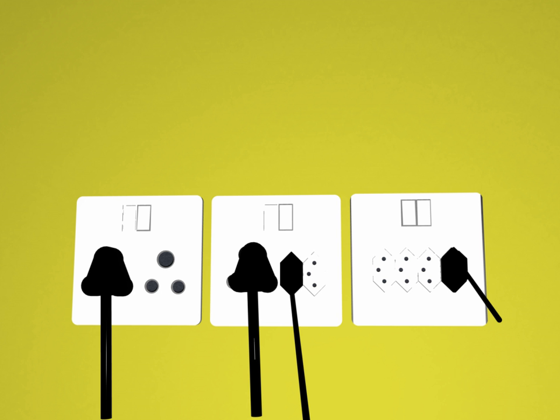Shock hazard can occur due to the possibility of class 1 equipment with Schuko plugs being inserted into commonly used 2-pin sockets that lack protective earth contacts. This can for instance be the case with the CEE 7/1 unearthed socket, which either have been or are currently being phased out in most countries.